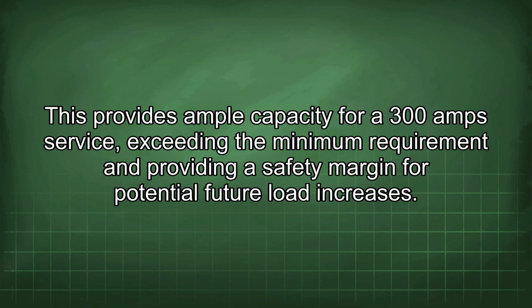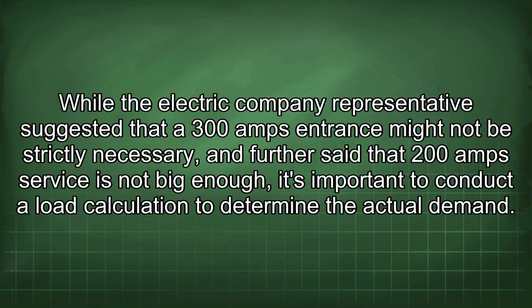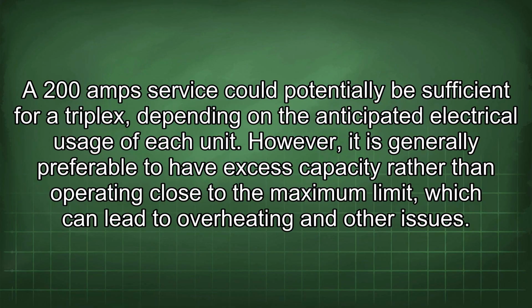future load increases. While the electric company representative suggested that a 300 amp entrance might not be strictly necessary, and further said that 200 amp service is not big enough, it's important to conduct a load calculation to determine the actual demand. A 200 amp service could potentially be sufficient for a triplex, depending on the anticipated electrical usage of each unit. However, it is generally preferable to have excess capacity rather than operating close to the maximum limit, which can lead to overheating and other issues.